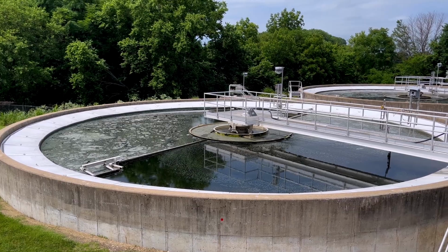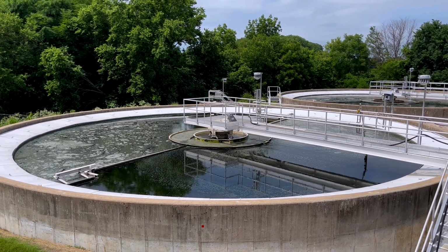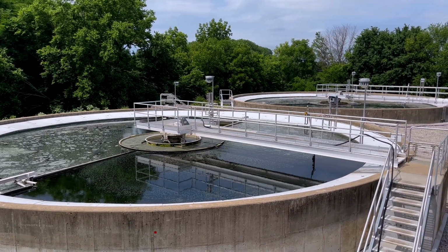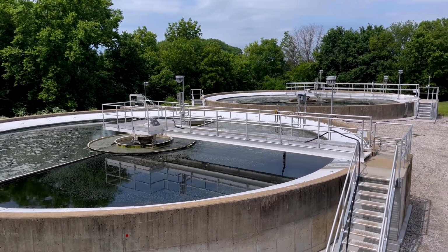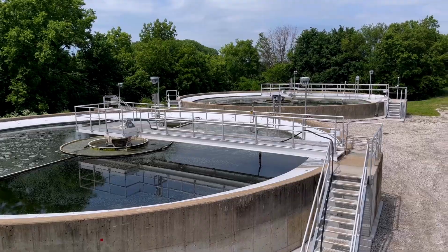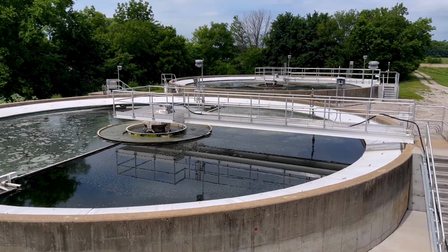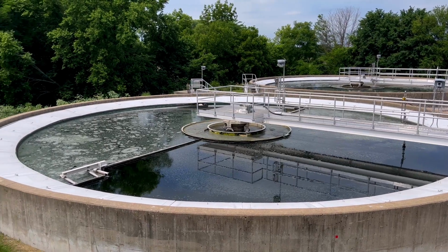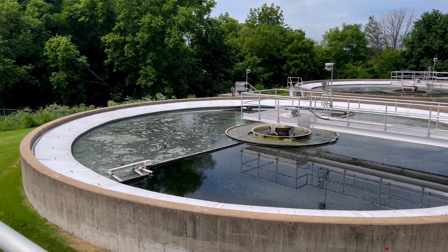The clarifier is a big tank that allows the wastewater to slow down so that the solids suspended in the water can settle to the bottom and clear water remains on top. The solids that settle to the bottom are either returned to the first channel, the aerobic zone, or they are removed from the process to the digesters. The clear water falls into the troughs and moves on to the ultraviolet light building.